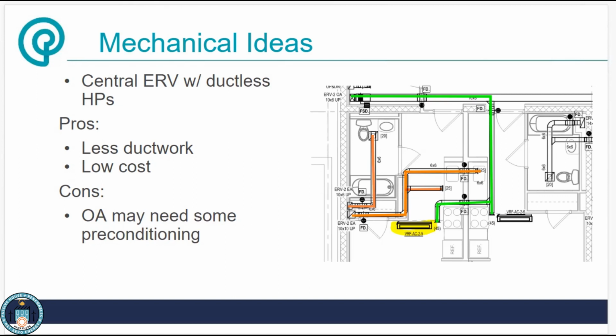Again, it's a little less ductwork if you're going to go with a ductless unit, and it works well in these studio apartments shown here. A more complicated apartment with a couple rooms in it will probably need some kind of a ducted system. And then also with this, some people still want to precondition that outdoor air, depending on the sensible recovery efficiency of the ERV. You could be supplying air that's either too hot or too cold for the space. So working out the math on that, and trying not to supply air less than 60 degrees Fahrenheit to the space, would be ideal.